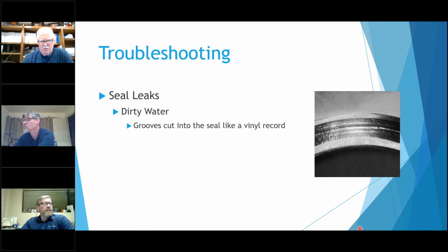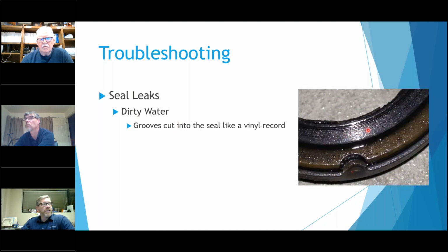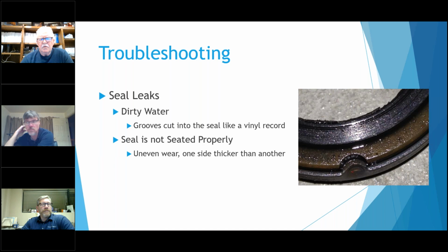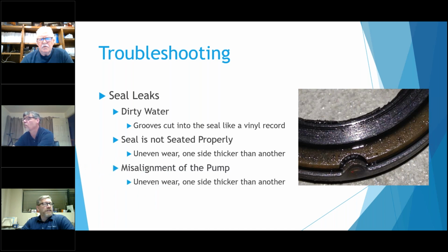So we've got this one here, it's dirty water, where you can see grooves cut into it, like the old vinyl record players, which I guess are making a comeback these days. This one's got a little bit better picture of the rotating face, where you can see these little lines in here. And we have unseated seals where there is misalignment. I've seen this where one side of the rotating face was completely worn down and the other side looked brand new.